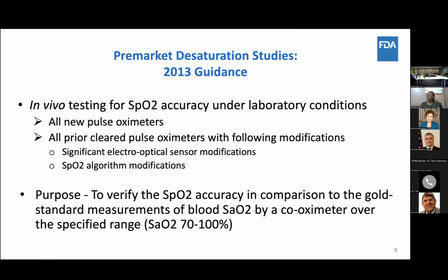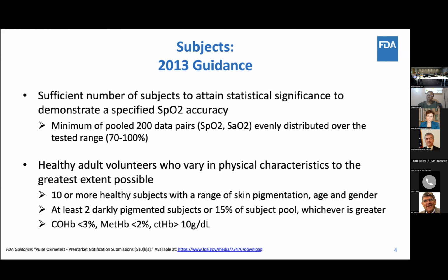So with that, we're going to go back to what is in place as of today. I believe I stopped here before. The 2013 guidance does recommend in vivo testing for SpO2 accuracy for all new pulse oximeters and all prior cleared pulse oximeters with modifications. I'll try to go very fast. The guidance does provide recommendations for pooled 200 data pairs, evenly distributed over the tested range. And again, the guidance makes recommendations for maximizing physical characteristics, but at the moment it only asks for at least 2 darkly pigmented subjects or 15% of the subject pool, whichever is greater.